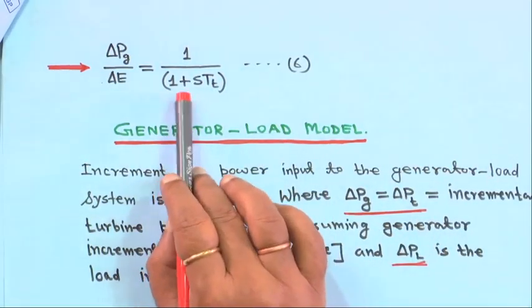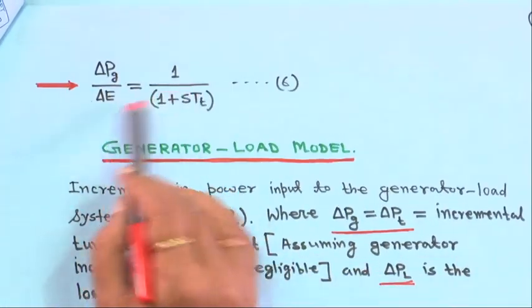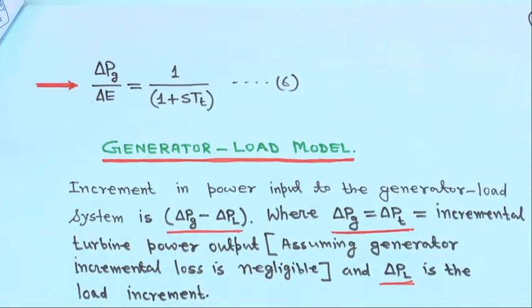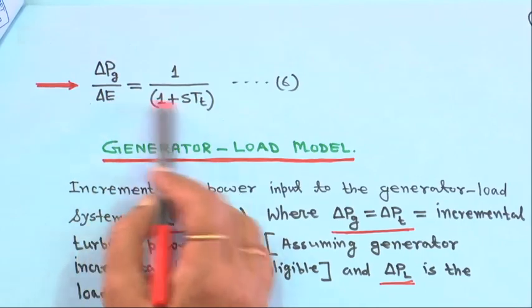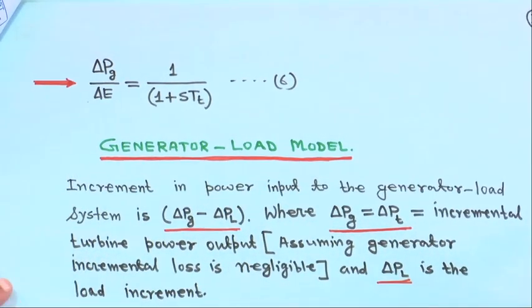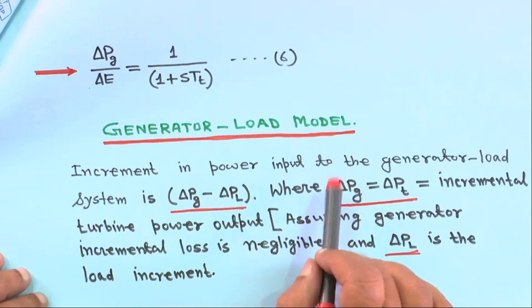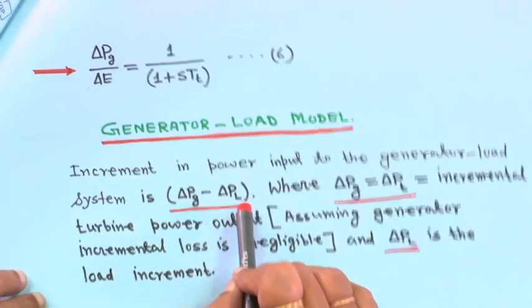So the turbine model gives us the relationship between delta P_G and delta E. For a non-reheat turbine it is 1/(1+sT_T), and for a reheat turbine it is (1 + s·K_R·T_R) / [(1+sT_T)(1+sT_R)], where K_R is the reheat coefficient — the fraction of power generated in the high pressure cylinder. This completes the turbine model section. Next is the generator load model.